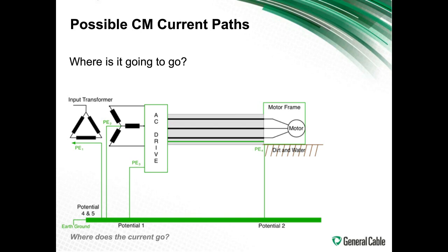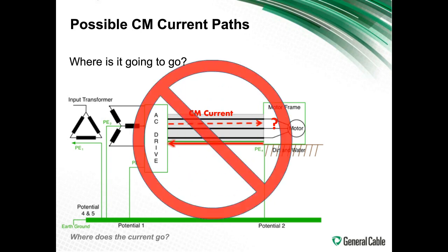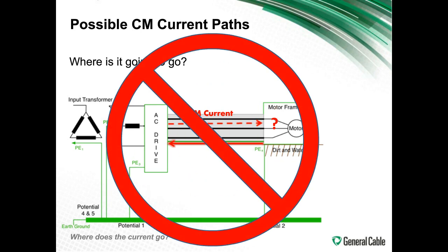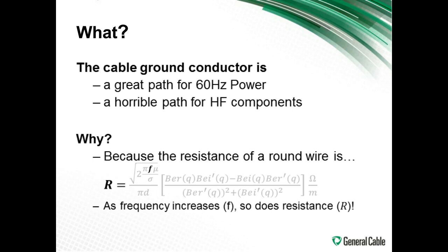There are several paths that this can take, and not good ones. You don't want it to go through the ground conductor. For a high frequency system, that is not a good thing. Now why? It's a really good path. A cable ground conductor is a really good path for 60 hertz power.